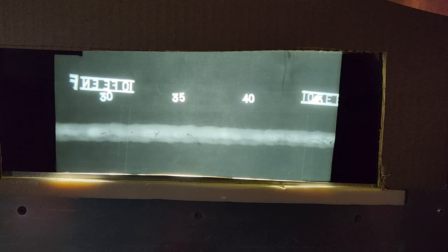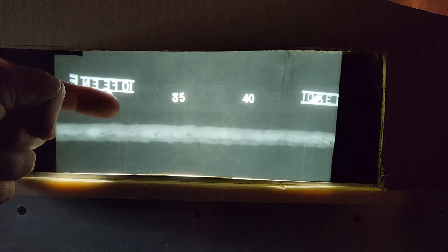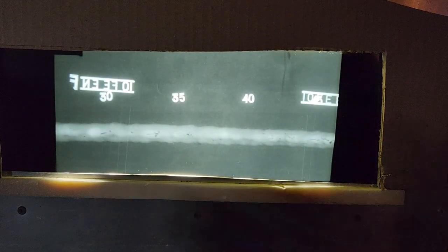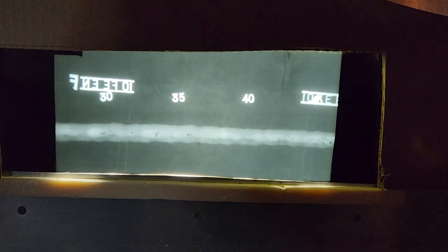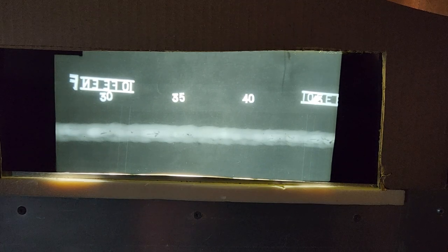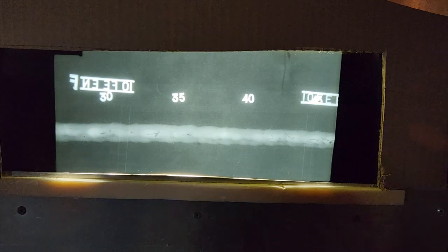We can see on this some of our IQIs are 10 FE, so we can start counting back some of our wires there and making sure they're right. But really, between the densitometer readings here and the IQI wires, and you can see we've got two IQIs because of the length of the sample, we can prove quality of the radiographic image and show that when I look at this image, I should have a high degree of confidence that any defects will show and I won't lose things because the quality isn't right.